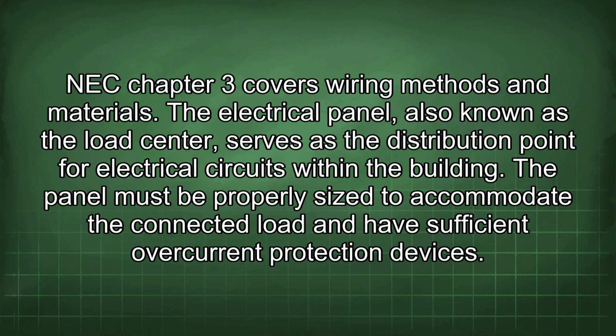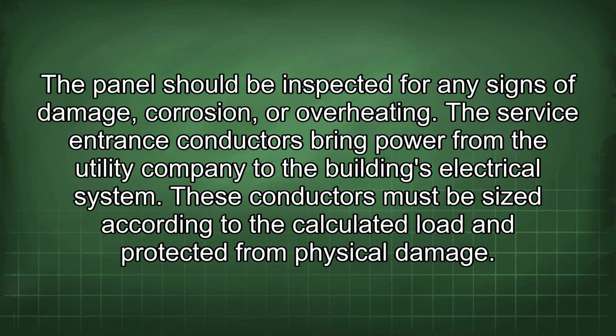The electrical panel, also known as the load center, serves as the distribution point for electrical circuits within the building. The panel must be properly sized to accommodate the connected load and have sufficient overcurrent protection devices. The panel should be inspected for any signs of damage, corrosion, or overheating.